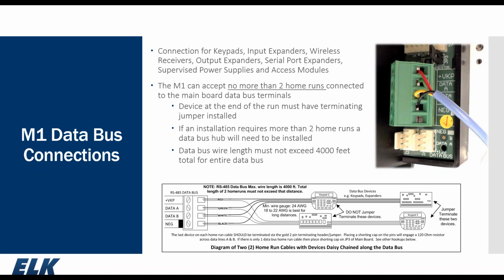With the RS-485 protocol, you can have a maximum of 2 home runs connected to the data bus. You can daisy chain devices going from one device to the next and so forth. And according to 485 protocol, the data bus must be terminated. Now, that process of terminating the data bus means installing a 120 ohm resistor across data A and data B.